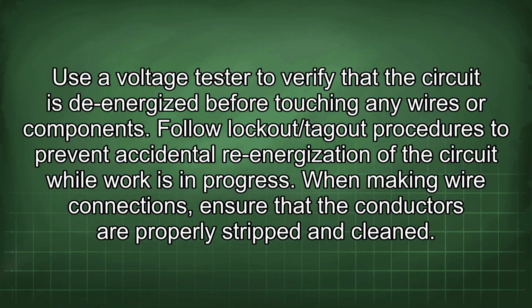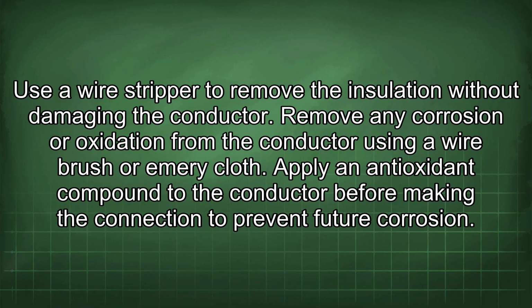When making wire connections, ensure that the conductors are properly stripped and cleaned. Use a wire stripper to remove the insulation without damaging the conductor. Remove any corrosion or oxidation from the conductor using a wire brush or emery cloth. Apply an antioxidant compound to the conductor before making the connection to prevent future corrosion.